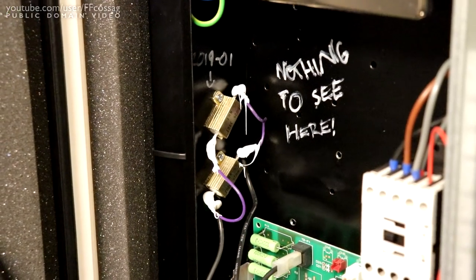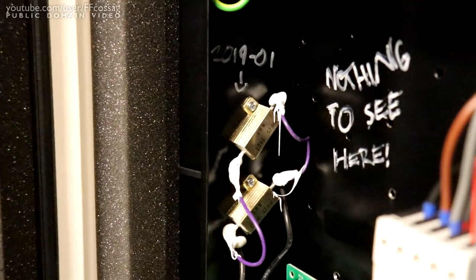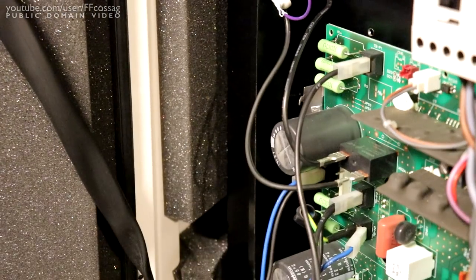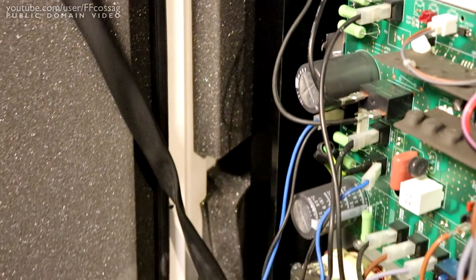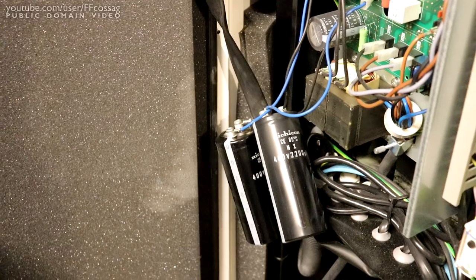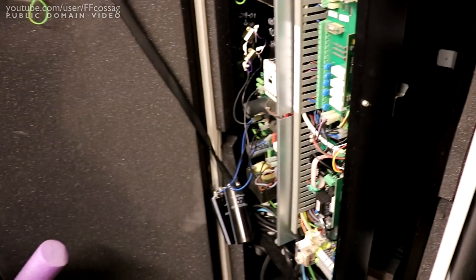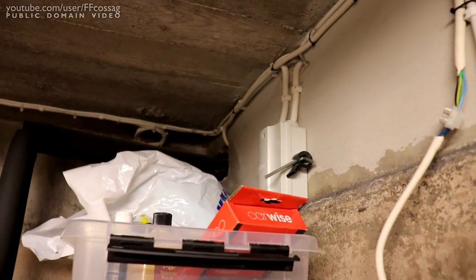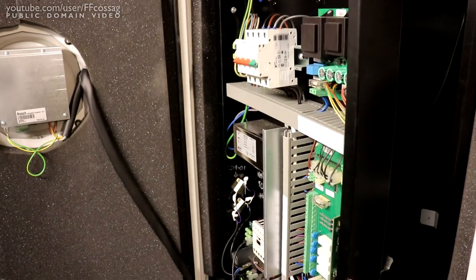Okay, I've finished repair so we have the two resistors bolted onto the case with the finest quality wood screws and they're hooked up and ready to go. So now all I have to do is mount the two big caps back together, put the rear cover back on. I had to take that off because I thought there were some nuts and bolts that were gonna fall off, there weren't. You can see the huge heat sink for the main VFD by the way, quite with the power being dissipated in that with the aid of a big fan but yeah just gonna put this back together and nothing left to do after that then but get our Allen key out of the safety interlock and give it a go.